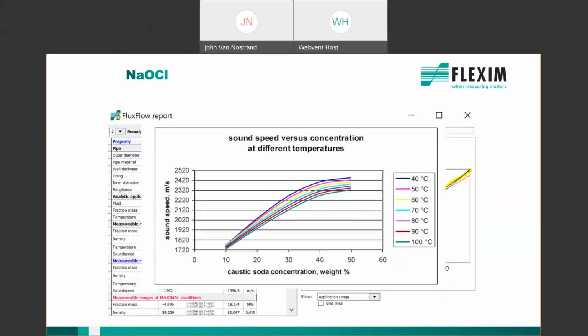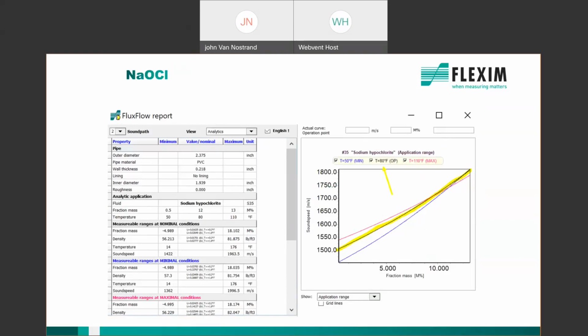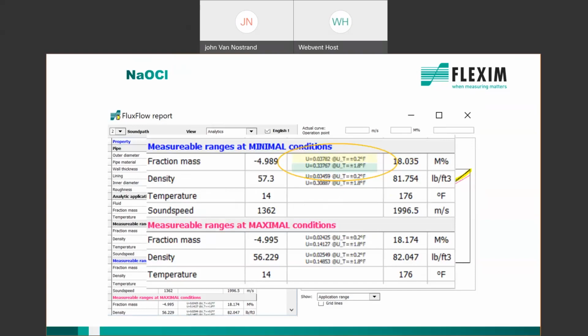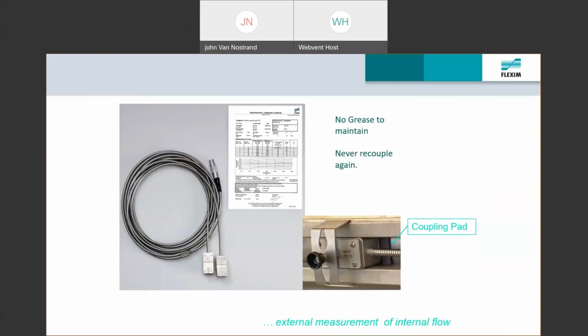Here's what that looks like a little bit more specifically. You see at different temperatures the sound speed changes slightly, and we correlate that temperature to the sound speed, and each of the different color lines indicates a different temperature. So we can calibrate that meter, set it up, and give you an actual value of what that sound speed should be at that temperature. We measure it and we report that value. So we give you a concentration value that is plus or minus 0.03% of weight. So we give you a very accurate measurement of the concentration value. That's just one of the things that we're capable of doing with the FLEXIM meter that other ultrasonic meters cannot do. So it's worthy of mentioning. And it's a very common application in the water market.